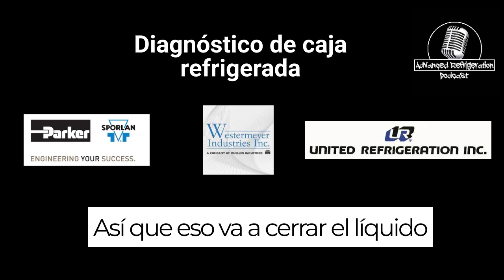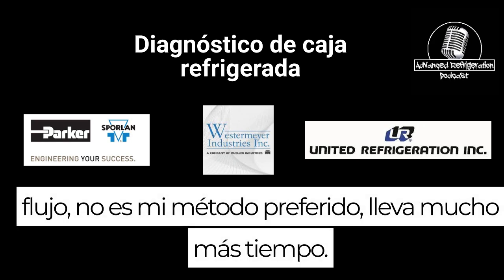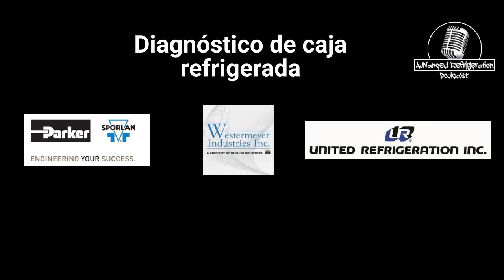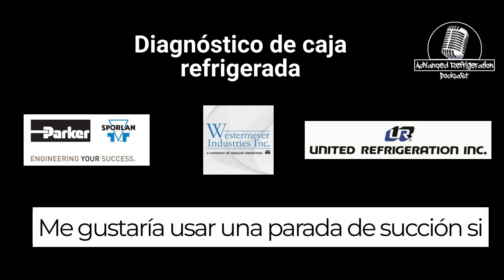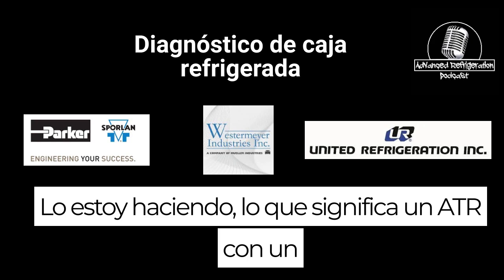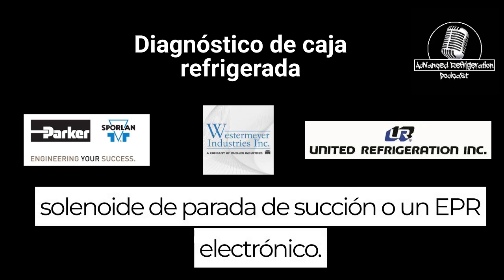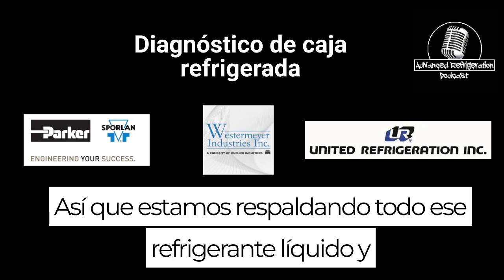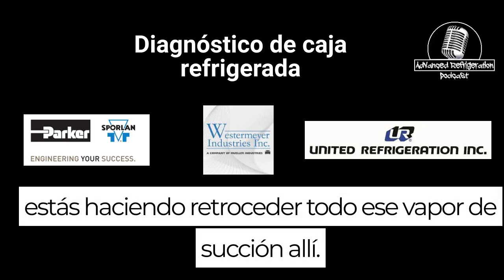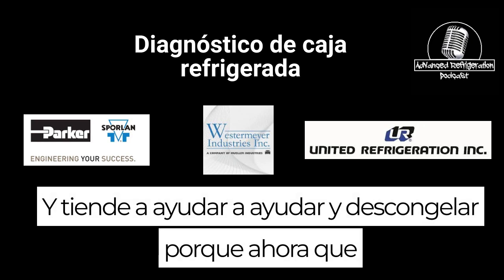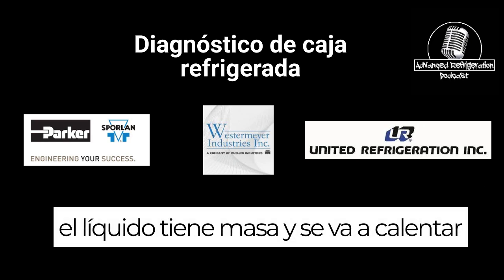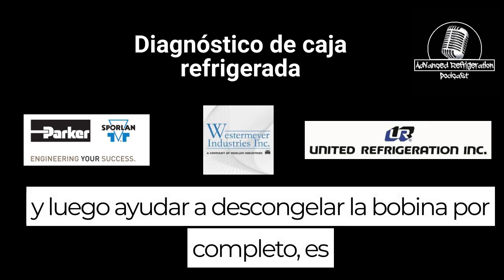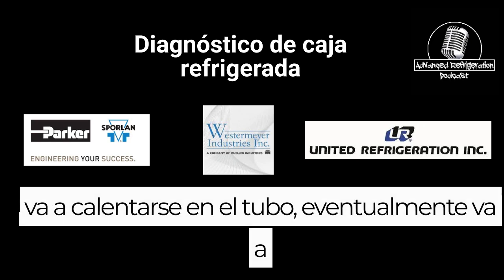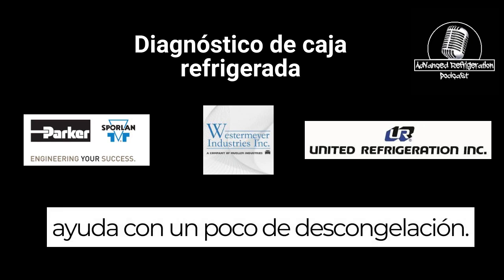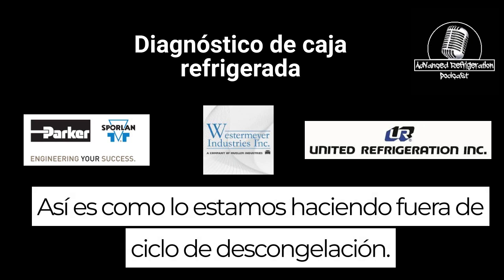So that's either going to be shutting off the liquid flow, not my preferred method of it. It takes way longer. I would like to use a suction stop if I'm doing it, meaning an EPR with a suction stop solenoid, or an electronic EPR. So we're backing up all that liquid refrigerant, and you're backing all that suction vapor up in there, and it tends to help aid in defrost because now that liquid has mass to it, and it's going to warm up and then help defrost the coil all the way through. It's going to warm up in the tube. Eventually, it's going to aid with a little bit of defrost. So that is how we're doing off-cycle defrost.